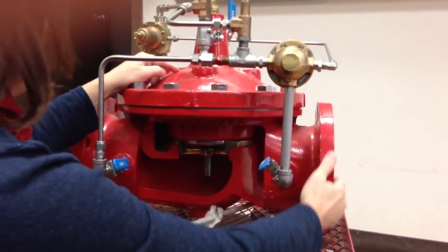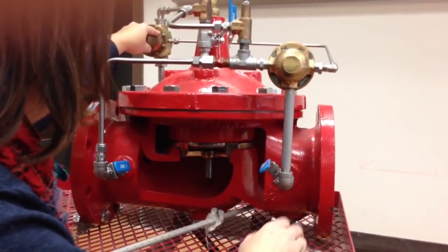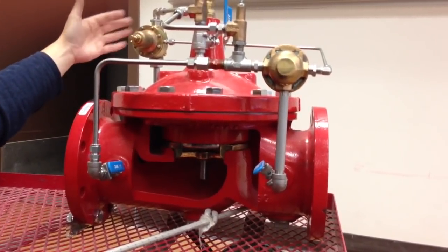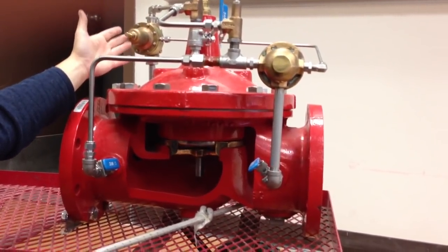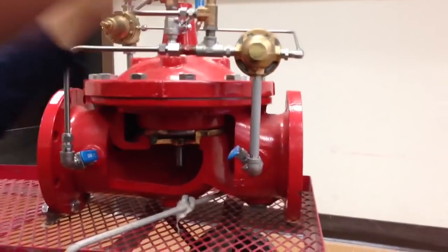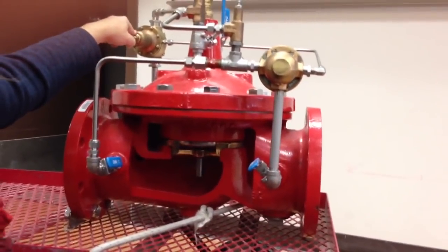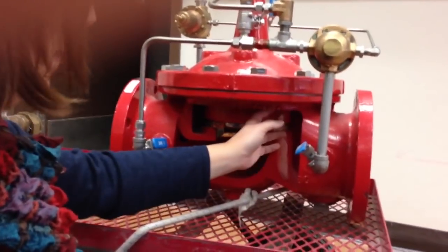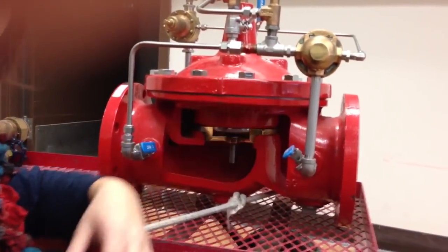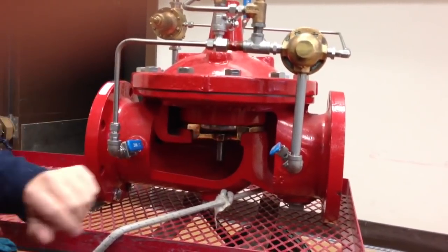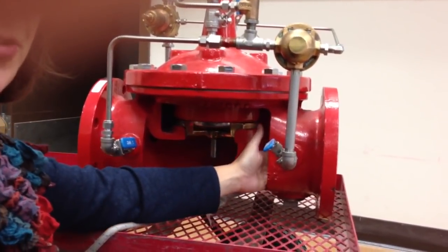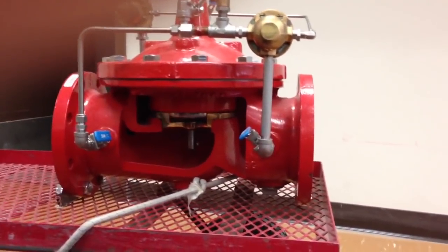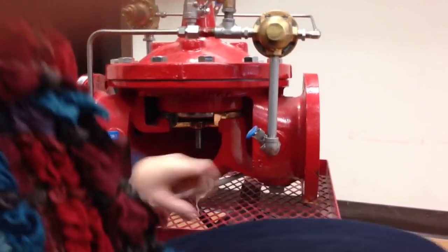So what we're going to do is set our CRL, or our pressure relief pilot, such that it's set at 5 or 10 pounds heavier than this one. If this one's set at 70, we'll set this at 80. So what's going to happen is, because this one fails wide open, the big valve starts to open also. It hasn't failed, but it will start to open wide up, and the pressure on the downstream side will start to rise. When it hits the 80 psi, some interesting things happen. Well, that one's always closed.